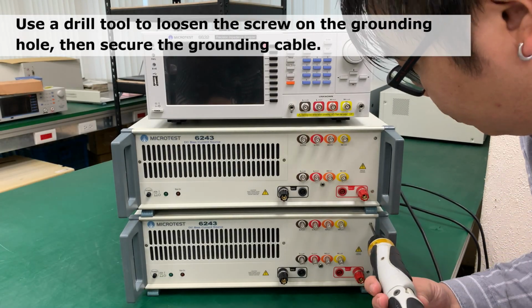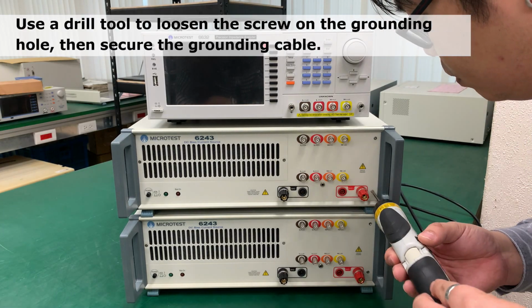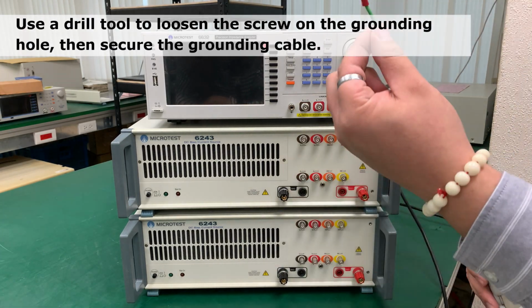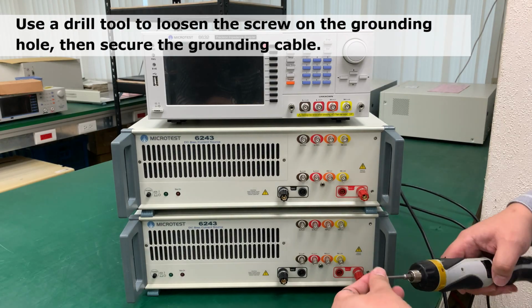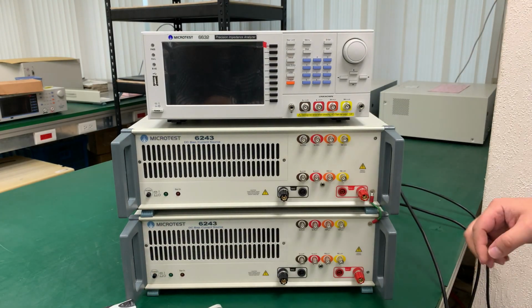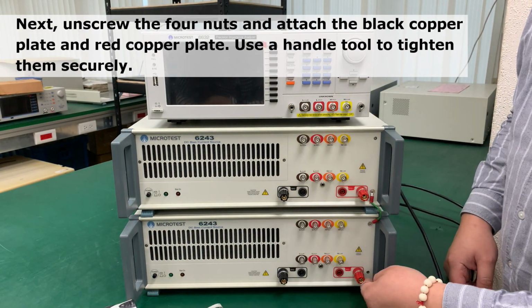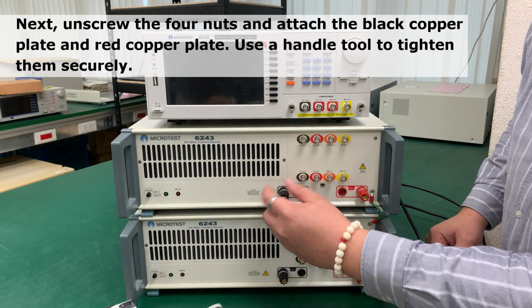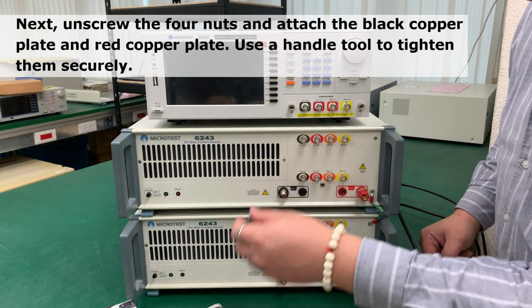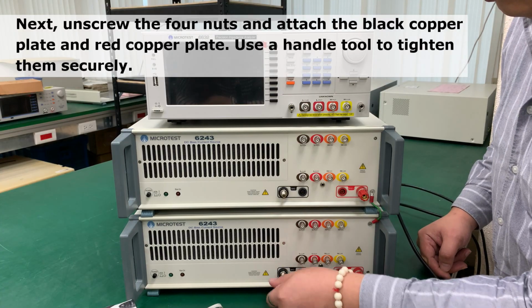Use a drill tool to loosen the screw on the grounding hole, then secure the grounding cable. Next, unscrew the 4 nuts and attach the black copper plate and red copper plate. Use a handle tool to tighten them securely.